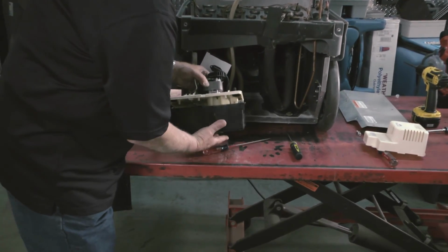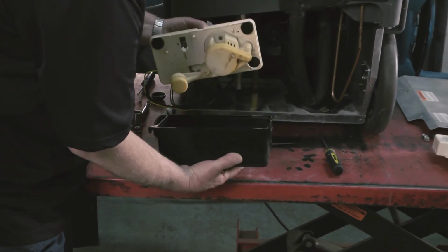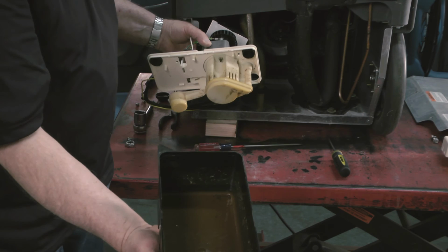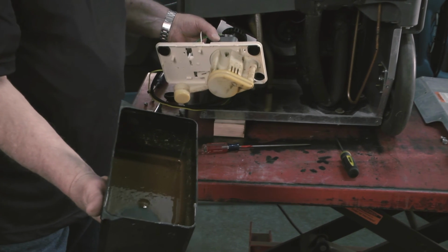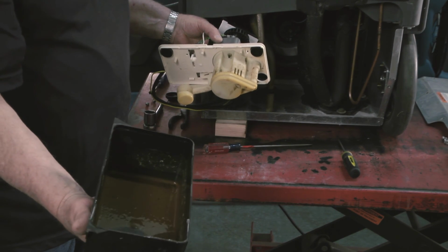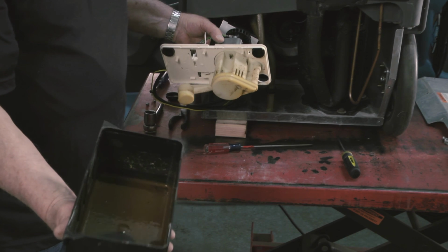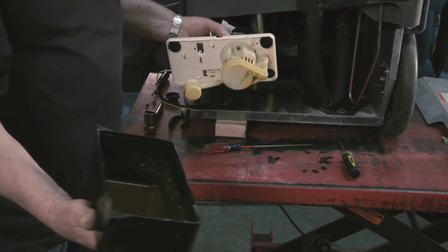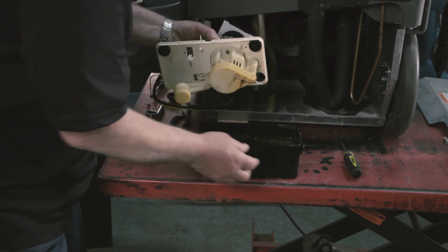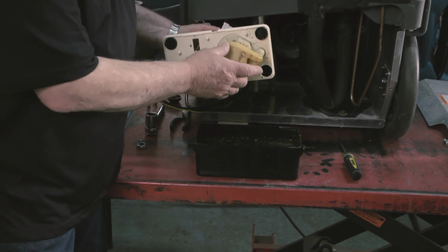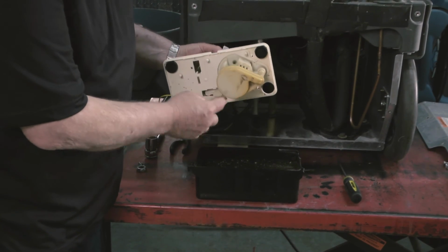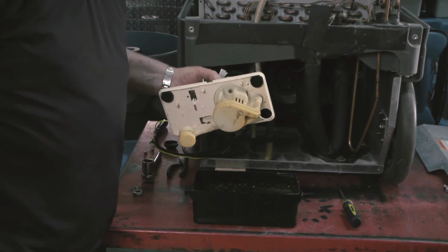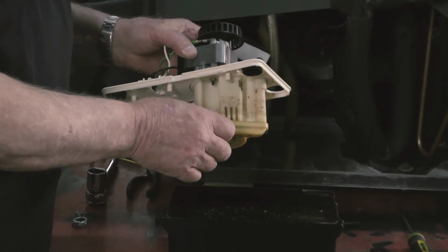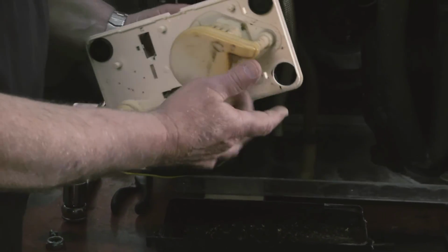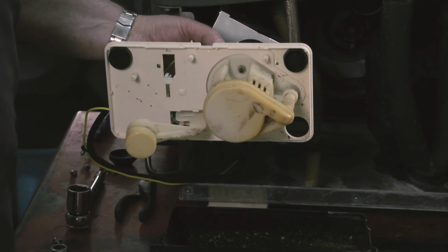What you want to do is take the basin off, and this one is dirty, so you want to clean that out. I normally just use a good strong source of water and flush it out and wipe it out as best I can. You want to look at the impeller cover. There's a gasket here. You want to make sure that that's not bulging. You want to make sure there are no cracks here from freezing or from chemicals.